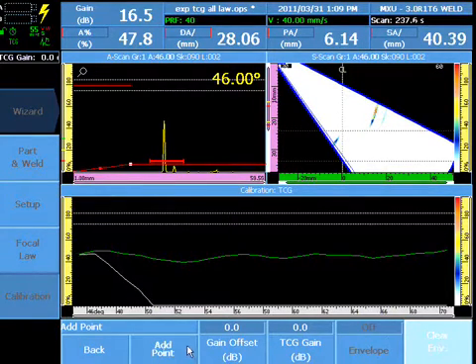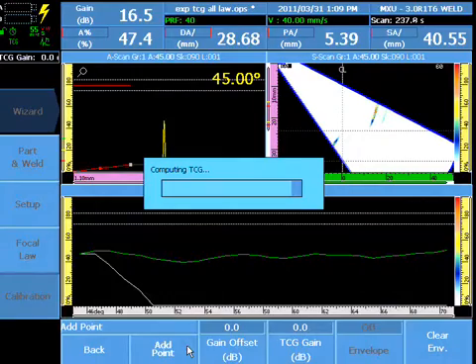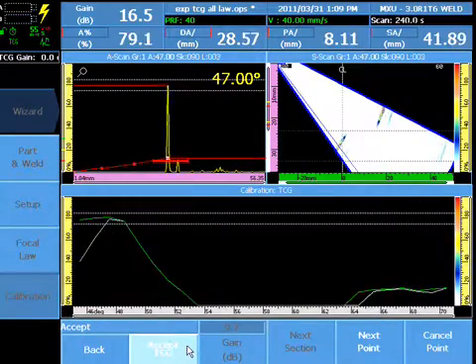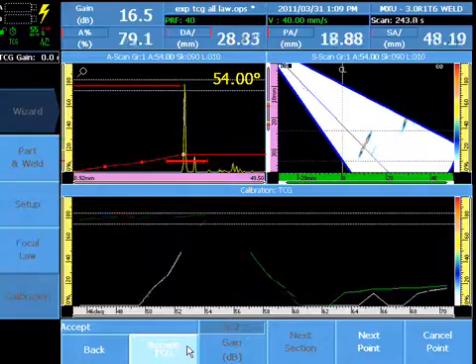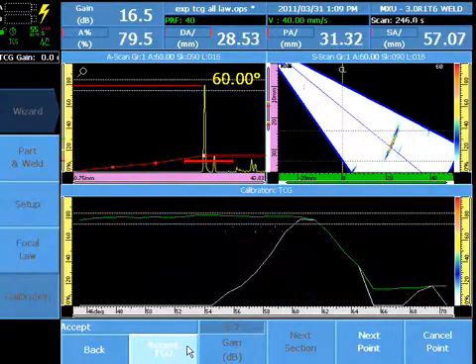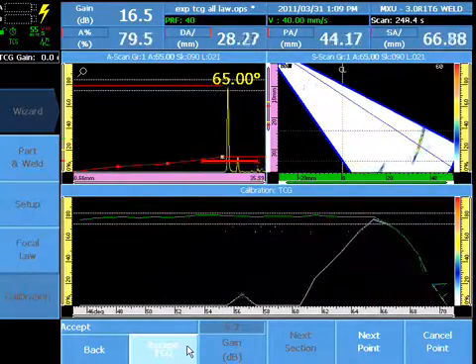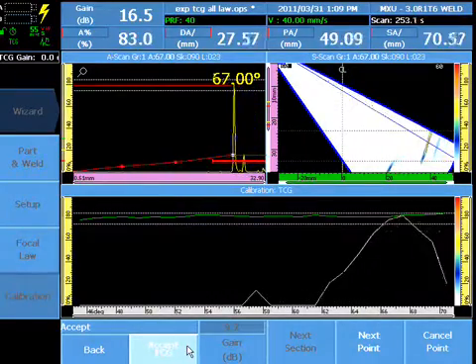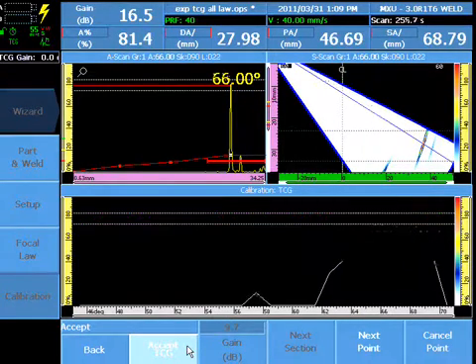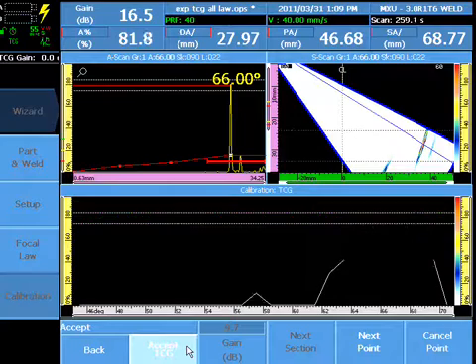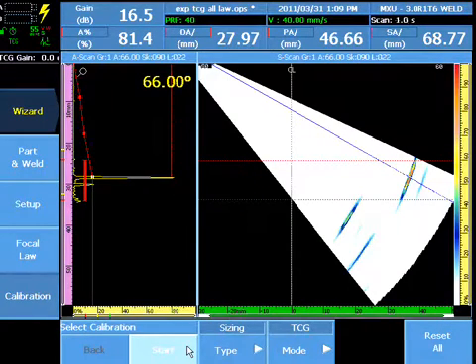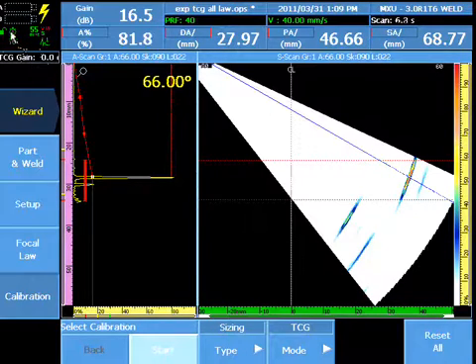Add the point. Verify that all points are at the correct amplitude for the TCG target. Continue to successive TCG points or accept the TCG. A green TCG is displayed when a TCG is active for the current group.